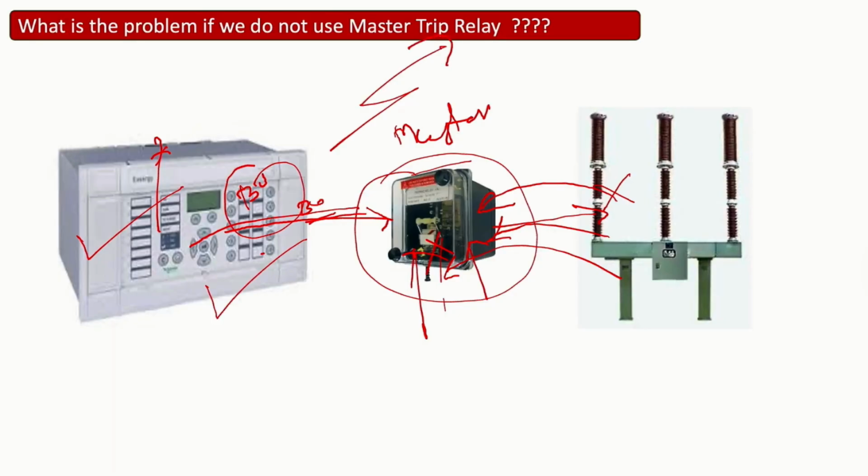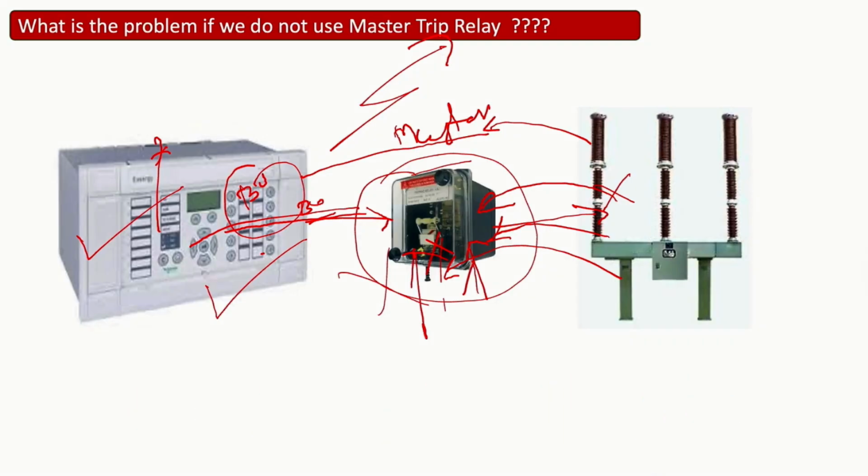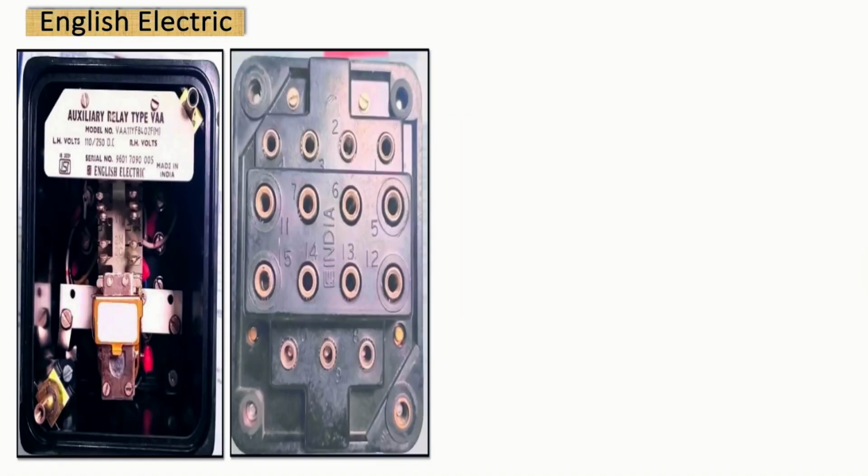So, you may have encountered a situation where the breaker didn't trip, and the relay's contact was damaged, where a master relay wasn't used. So, what should you do? In a situation where there's no master relay, and the breaker didn't trip, you must conduct a mandatory tripping test on the relay. The relay has a tripping function built into it. So, you should perform the tripping test.